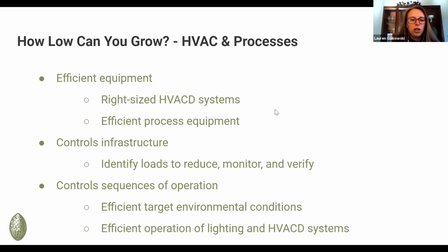Also just making sure that we're controlling to a set point that's achievable. I always talk to HVAC manufacturers, and growers are asking for almost impossible relative humidity and temperature set points. That's not necessarily necessary, right? You can grow with LEDs at higher temperature and relative humidity, and that's just going to require less work on the HVAC equipment.